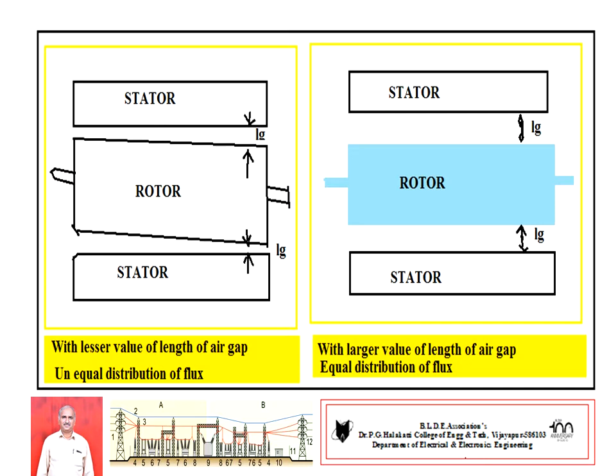Hence, the distribution of flux also takes place non-uniformly. This will cause a pulling effect. It is also known as unbalanced magnetic pull. This unbalanced magnetic pull will cause the pulling effect. This effect will be more when a lower value of Lg is used. This effect might be less when the length of air gap is larger value. Hence, again the best choice is a larger value of Lg should be used to keep the UMP less.